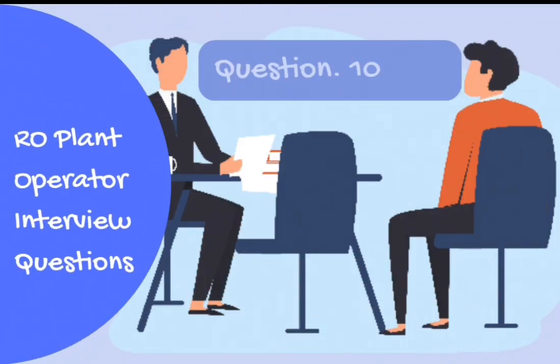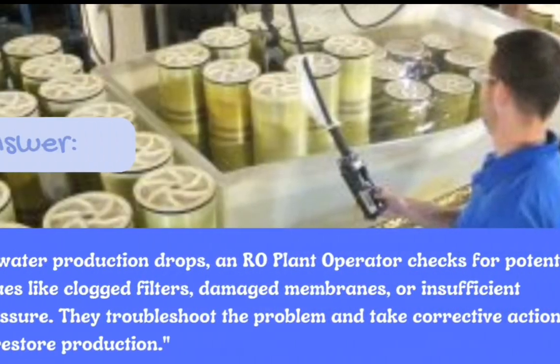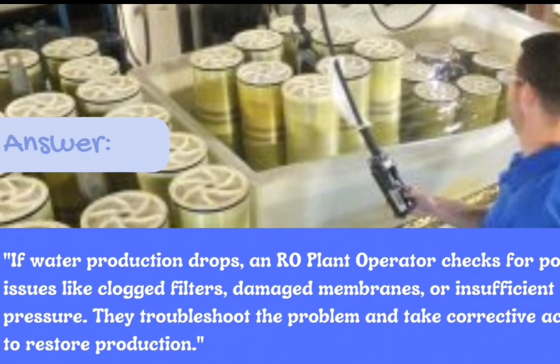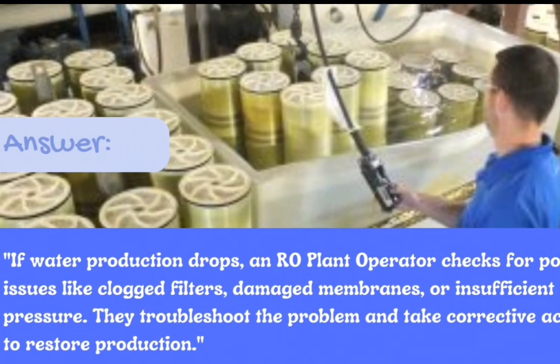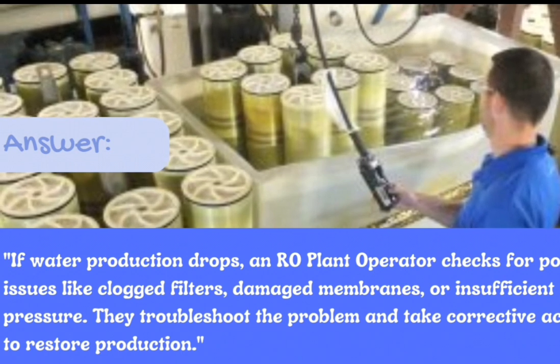Question number 10: How do you handle a drop in water production? Answer: If water production drops, an RO plant operator checks for potential issues like clogged filters, damaged membranes, or insufficient pressure. They troubleshoot the problem and take corrective actions to restore production.